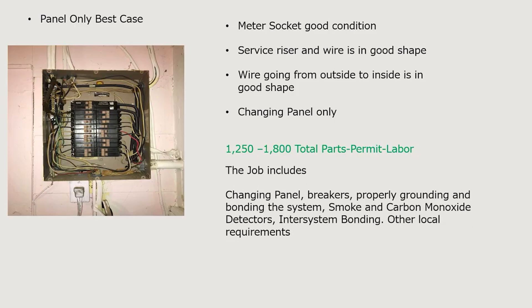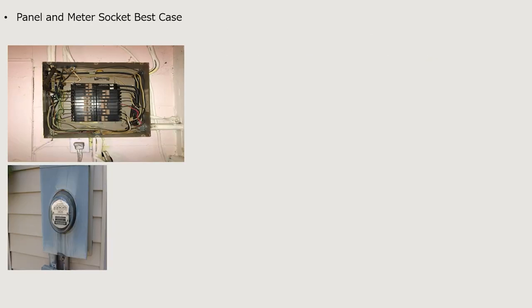This job includes changing the panel, installing new breakers, properly grounding and bonding the system, installing smoke and carbon monoxide detectors where required by code, installing an inter-system bonding strip, and other local or NEC requirements. This is a pretty standard best-case scenario price. There are things that could push it higher. If you get a price around $800 to $900 including parts, be very careful — if it sounds too good to be true, it usually is.